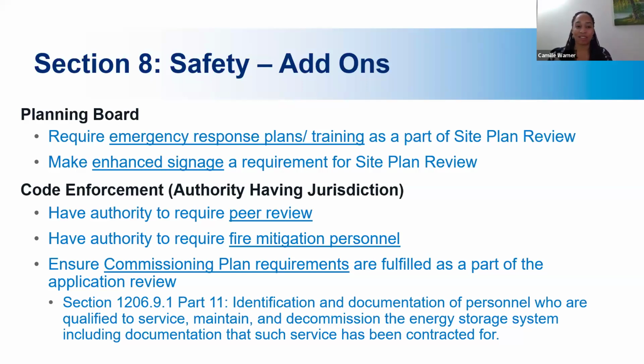The last one is a commissioning plan. This requires the AHJ, the code enforcement officer, to have proof of an emergency response team—you shouldn't have to do anything yourself. There are 12 requirements of the commissioning plan, and requirement 11 is that the developer needs to prove they have a contract with an entity that will respond to an incident and dispose of a battery system.